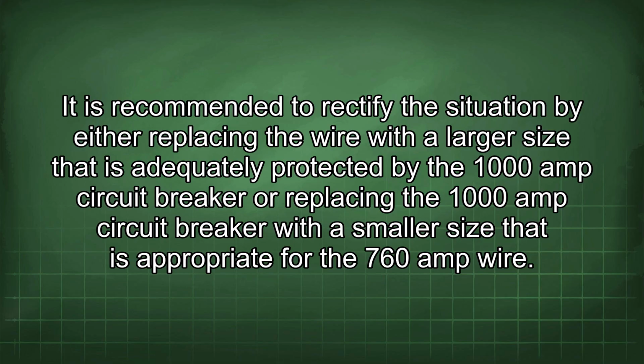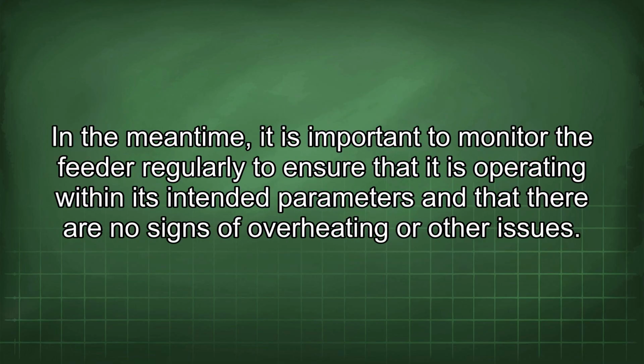It is recommended to rectify the situation by either replacing the wire with a larger size that is adequately protected by the 1000 amp circuit breaker, or replacing the 1000 amp circuit breaker with a smaller size that is appropriate for the 760 amp wire. In the meantime, it is important to monitor the feeder regularly to ensure that it is operating within its intended parameters and that there are no signs of overheating or other issues.